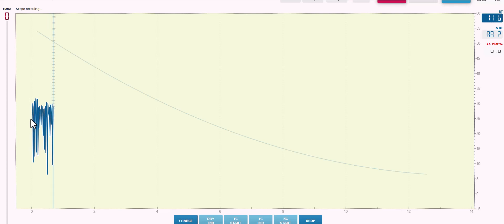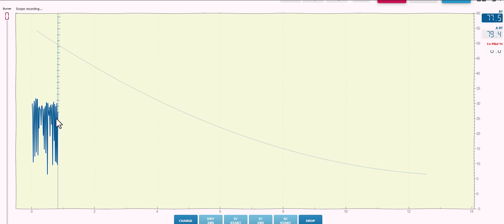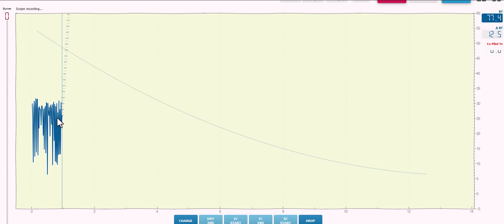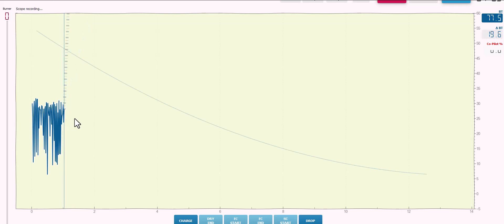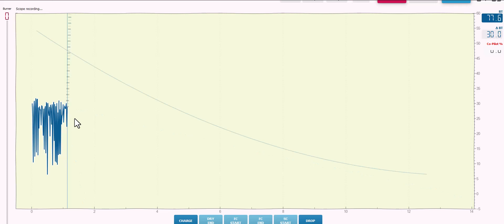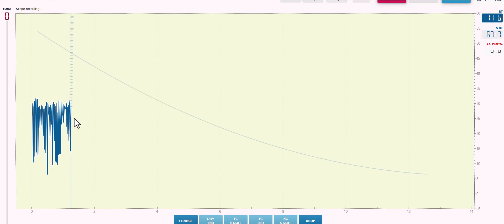Now there can be a number of reasons for this. There are just cheap thermocouples and sometimes they're just like this because it's a trash thermocouple. So starting out with a quality measuring device is an important step one. But sometimes you get lucky and even a cheap Amazon thermocouple can give a clean reading. But in this case, I'm using a Yocto thermocouple device and Yoctos are not electrically isolated from the USB port, which means that your computer's USB port goes into your common ground in the house and it can create a ground loop.